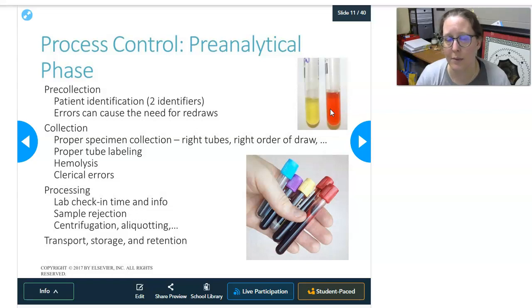Oftentimes, too, we talk about that in automation. If the samples aren't checked in, then the information doesn't cross over from the LIS into the analyzer. And if you load a tube on your analyzer that hasn't been checked in, the analyzer doesn't know what to do with it, so it does nothing with it. And then you could be thinking that the sample's running, when indeed there's actually nothing going on. Anyway, also how it's transported to the lab, how it is stored after it's collected, whether or not you retain the sample or it's thrown away. If you do retain, which a lot of times we do retain our samples, how long do you retain it for? Do you retain it for the duration of the shift, 24 hours, 48 hours, 5 days, a week? Like, how long do we keep them?